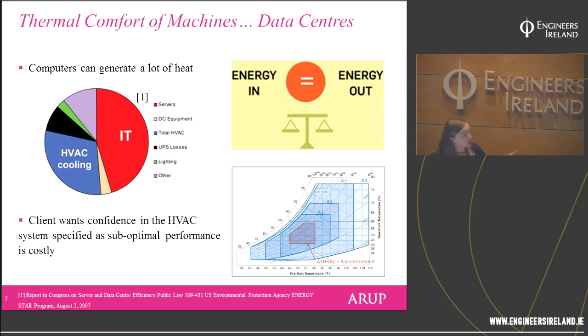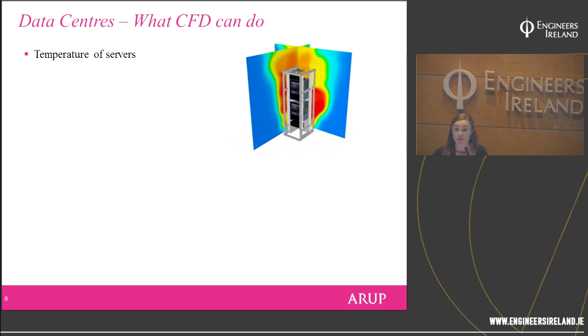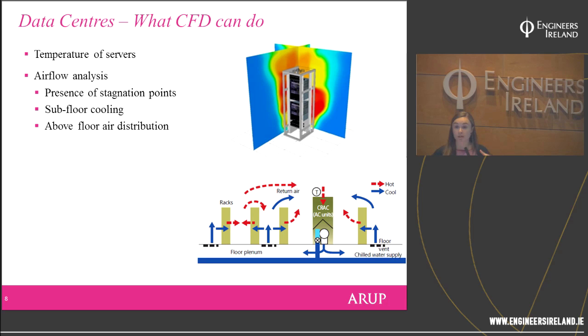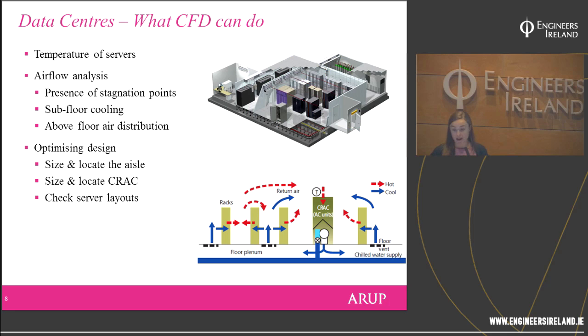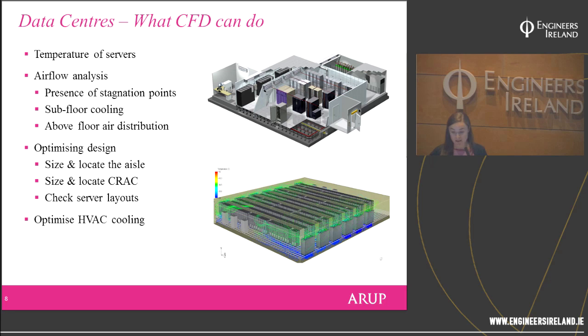Our clients want confidence that the data centre and the HVAC system specified will perform optimally. With CFD we can look specifically at server temperatures, how they heat up and cool down, whether there are stagnation points with very hot or very cold zones and insufficient mixing. We can examine where cooling units and floor grills are placed, and ultimately optimize the cooling system for a particular data centre design.